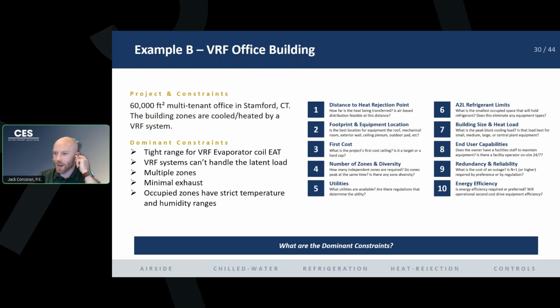Example B, right? So now we have a VRF office building. It's 60,000 square feet, multi-tenant in Stamford, Connecticut. And we know that the system that's going to be throughout the space is a VRF system. And we need to bring the outside air to each of the zones. So we discussed just a little bit earlier, in our previous presentation on VRF, that the VRF evaporator coils, the fan coil units, can't handle the latent load. So you need a DOAS system or fan system that can provide that latent cooling before it gets to this downstream coil. We're going to have many, many zones, and there's minimal exhaust.